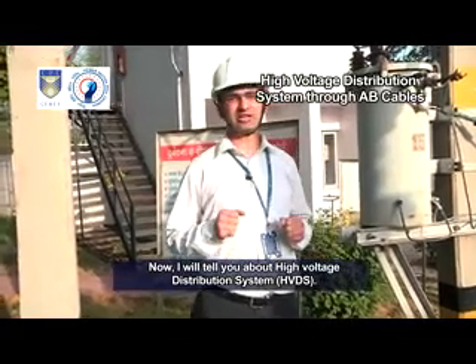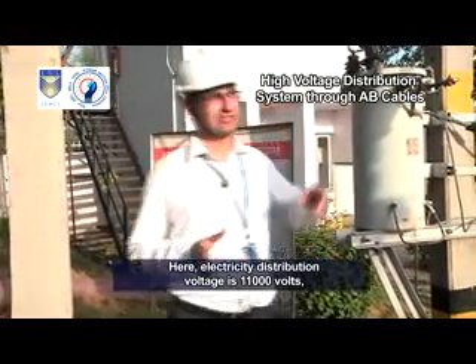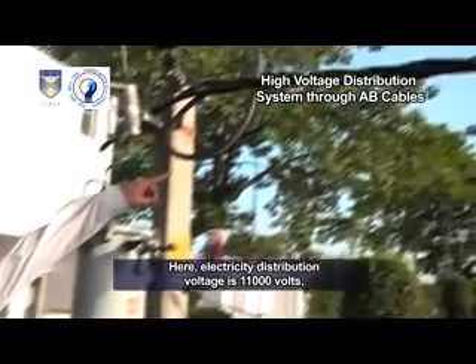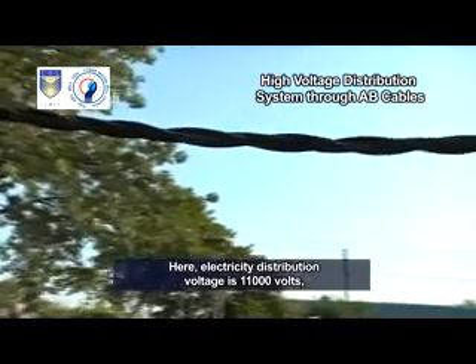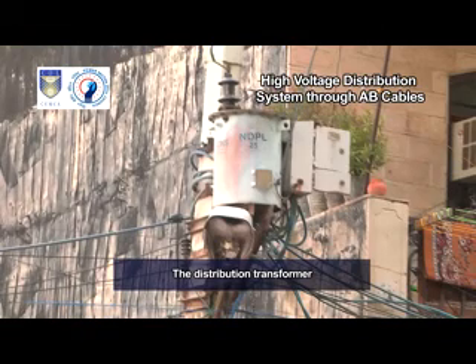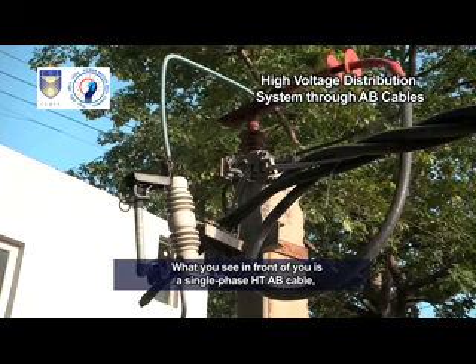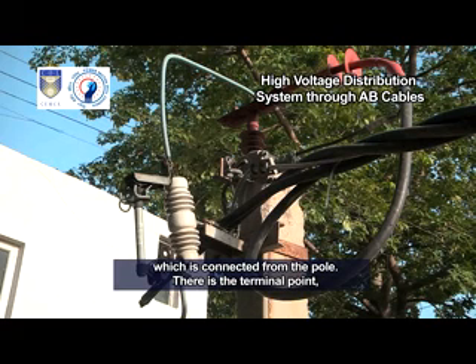I will tell you about high voltage distribution system HVDS. Electricity distribution voltage is 11,000 volts, supplied through aerial bunch cable ABC. The distribution transformer is installed at the doorstep of the consumer to step down voltage to the usable level. What you see in front of you is a single phase HT AB cable which is connected from the pole.